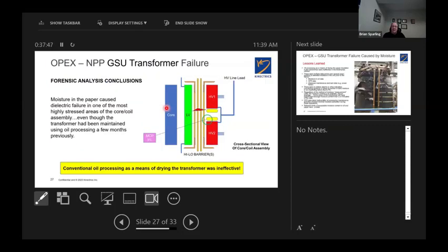Now back to that case I showed at the beginning, that GSU, that single phase, in the forensic analysis. Moisture in the paper caused this dielectric failure, in this case in one of the most highly stressed areas of the core and coil assembly. So you can see this high voltage lead coming in, and this is on extra high voltage transformers. This is a common way to bring the power in. You have two high voltage sections. And by again going in and taking out paper samples, we managed to find the point where it failed. It was through the barrier, high voltage to low voltage winding, where it happened.